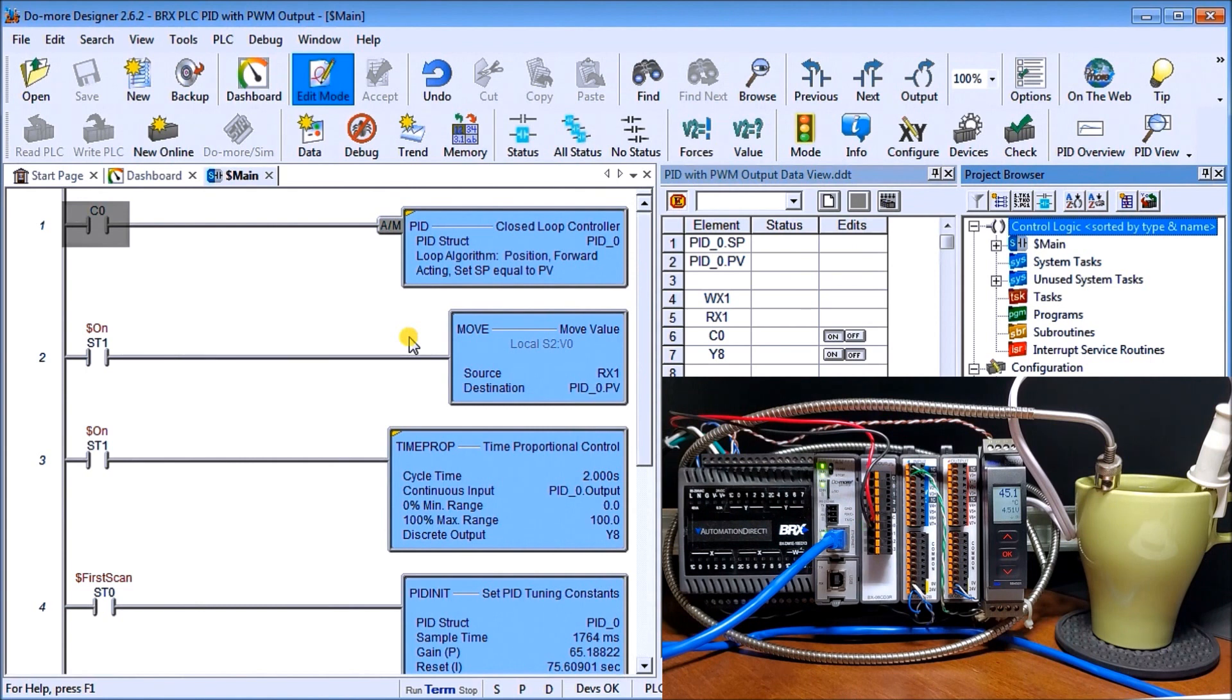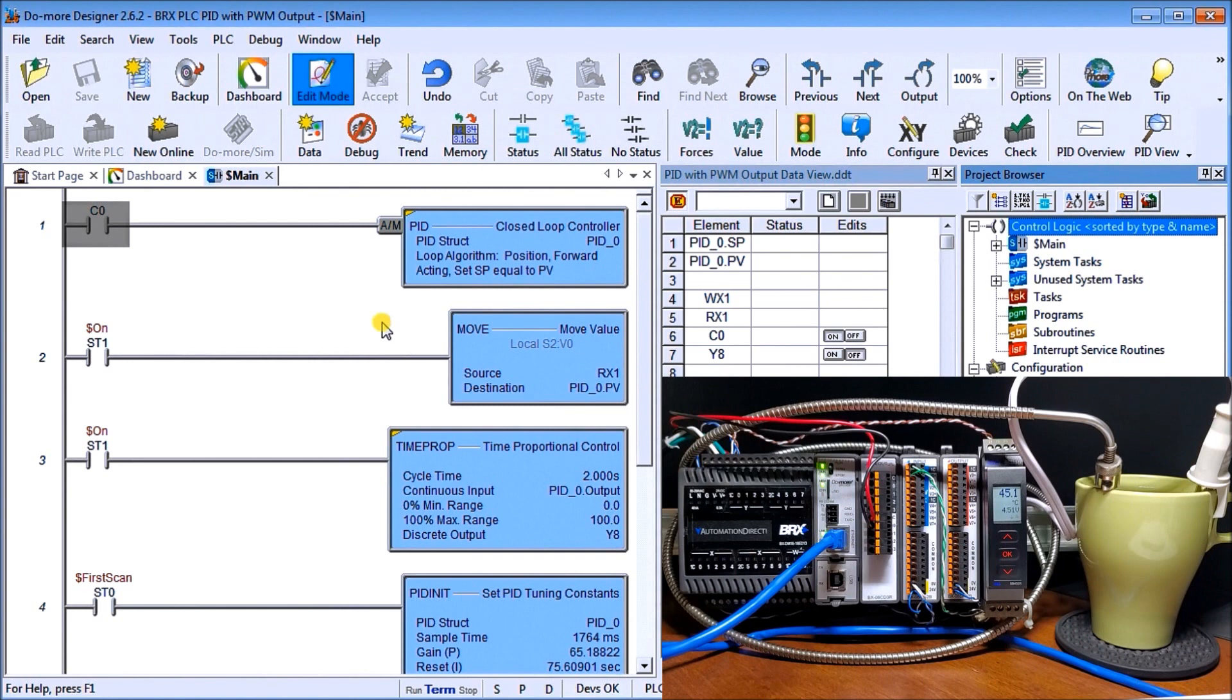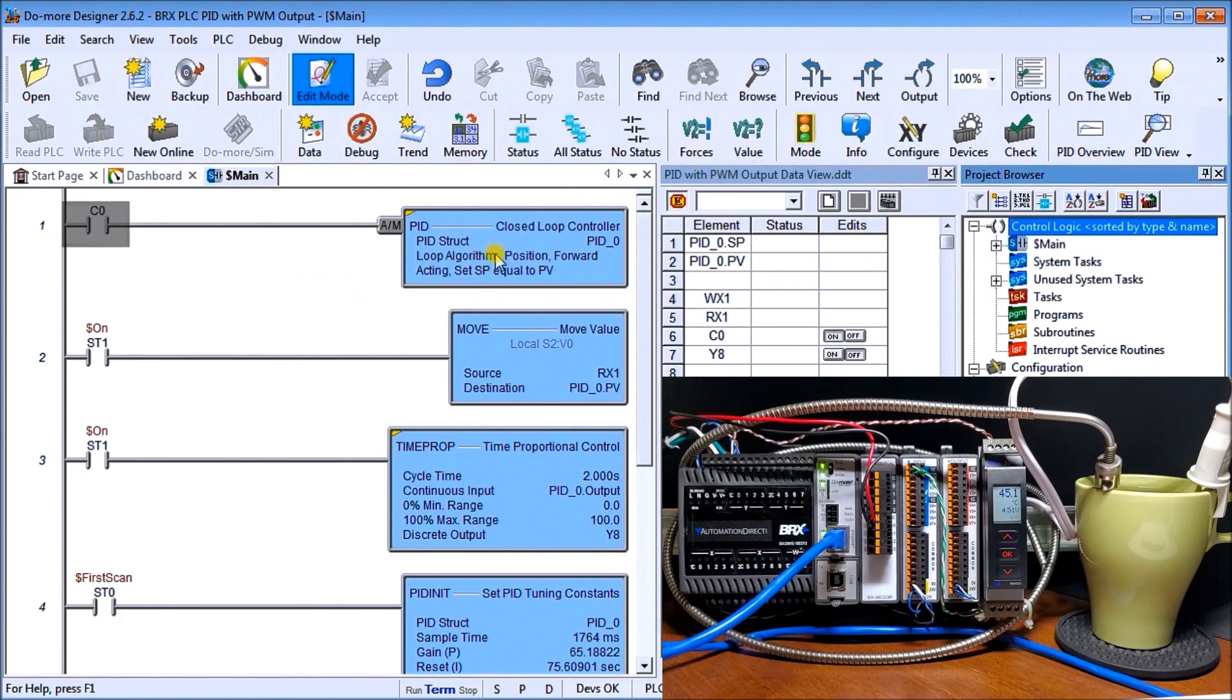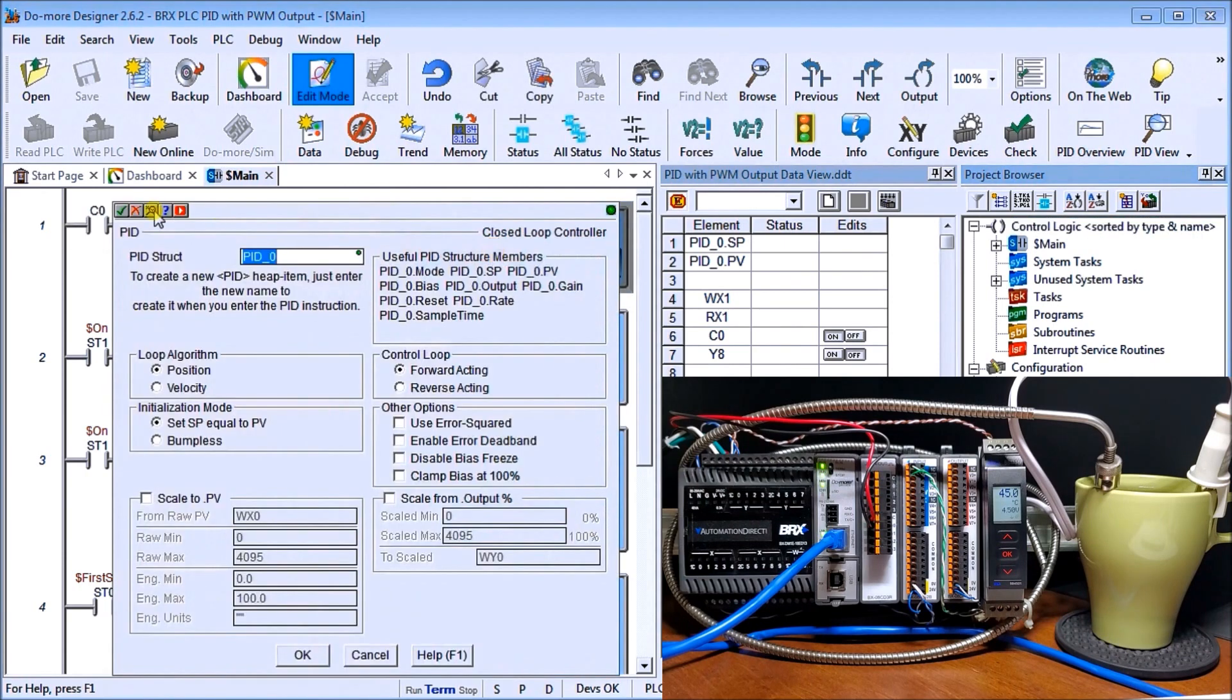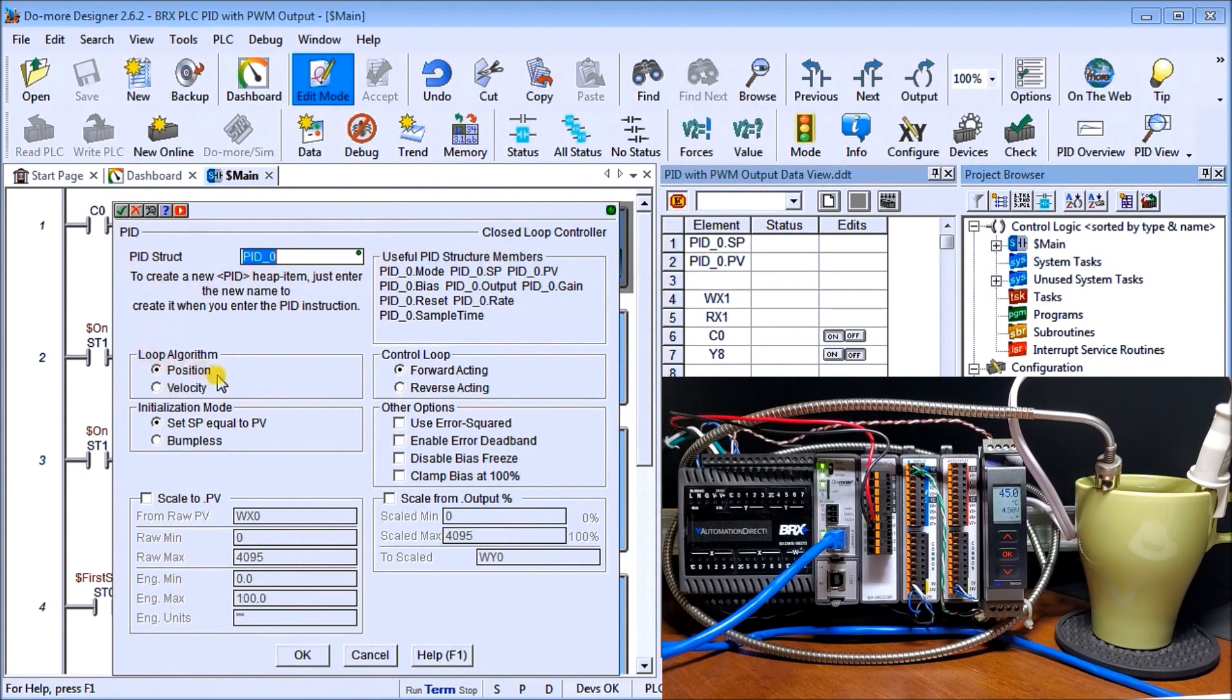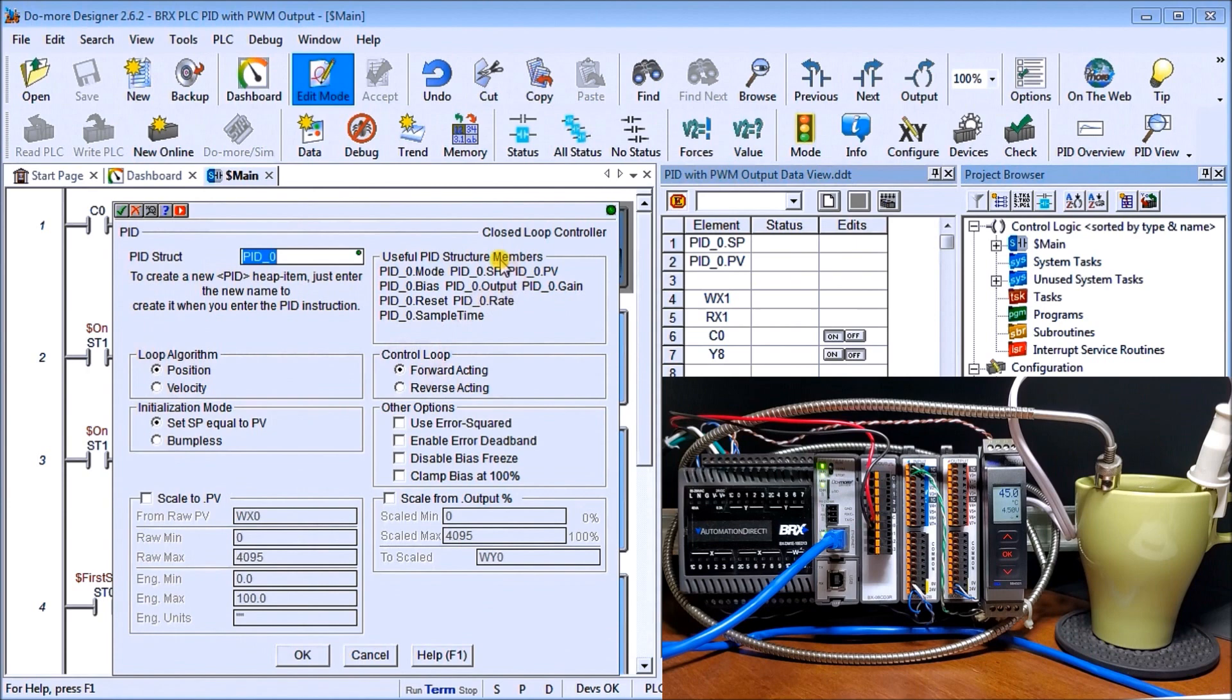What we're going to do is use the PID instruction within the DoMore Designer software. On my screen you'll see our ladder logic. If I click on my PID closed loop controller, our PID structure is PID 0, our loop algorithm is position, the control loop is forward acting. It will predetermine and establish these parameters for me: my P, my I, and my D, my present value, my set value.